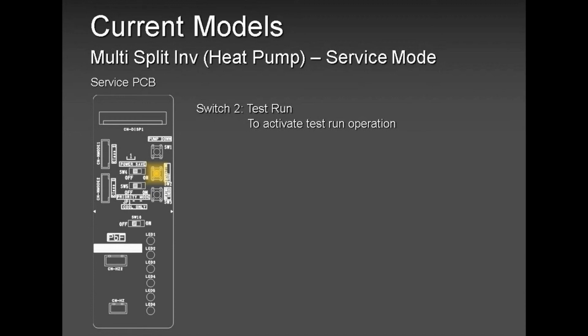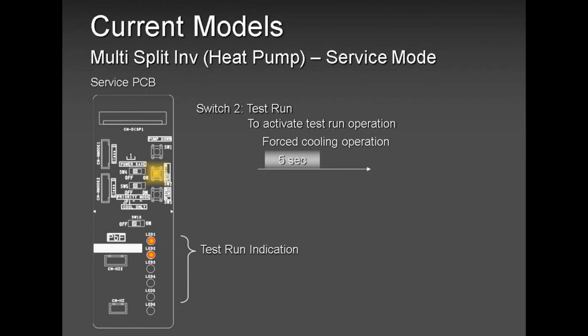So basically what pump down is, the compressor is running at a fixed frequency, all the electronic expansion valves are fully open, and the indoor units are forced to run in cooling. Make sure you close the liquid line. When the pressure is just about to get below vacuum, you will see the light indication telling you what is going on. When you see those lights flashing, it means 3 minutes are remaining. When one light goes off and only 2 are flashing, it means 2 minutes. When one light flashes, 1 minute, and you're done. Quickly close the suction line, and you're good to go.